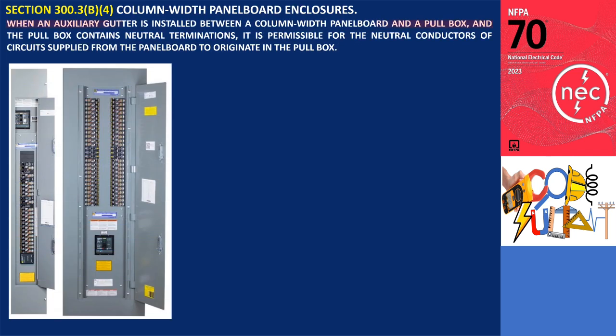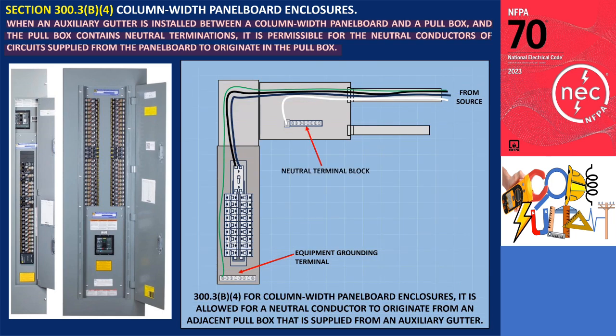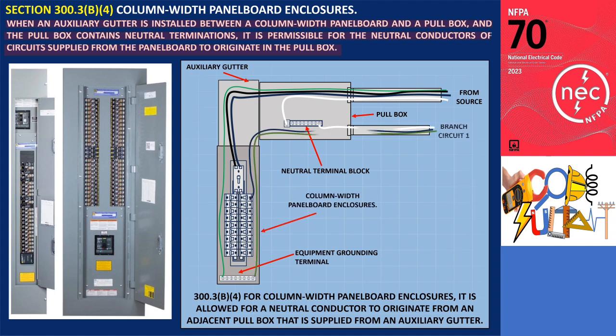Section 300.3b.4 permits the limited use of a pullbox equipped with a terminal block for the connection of the system neutral, as the point of origin for branch circuit neutral conductors. A properly sized neutral is run to the pullbox, which is connected by an auxiliary gutter to a column-width panel board. From the panel board, the individual branch circuit neutrals may be run from the pullbox and need not go back to the panel board where the hot conductors originate. This saves space within the panel board but is only permitted for column-width panel boards connected by an auxiliary gutter to a pullbox that is manufacturer equipped with a neutral terminal block.